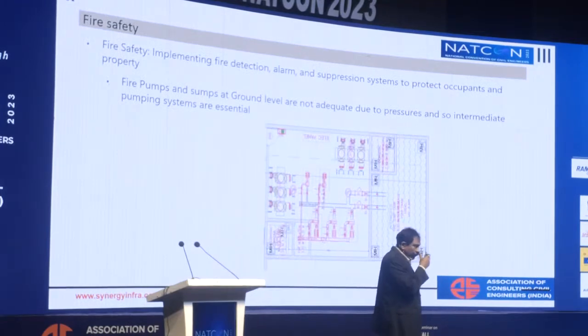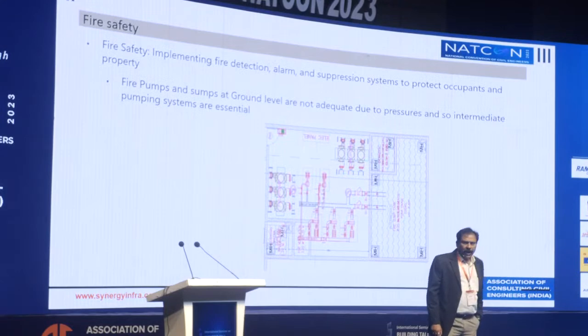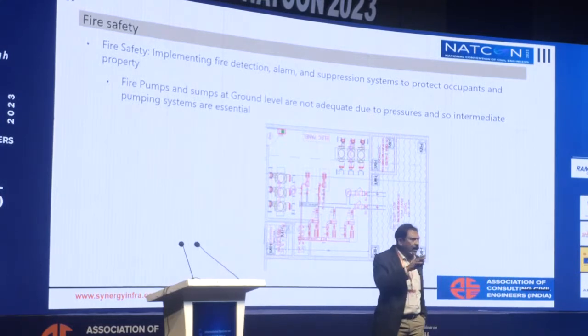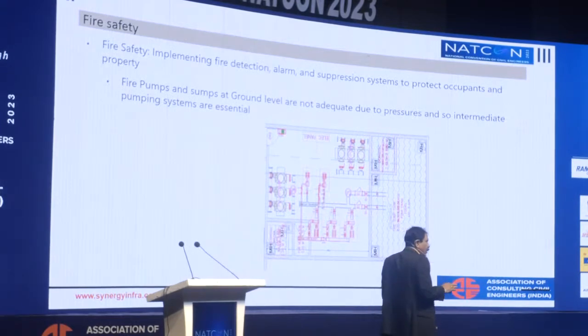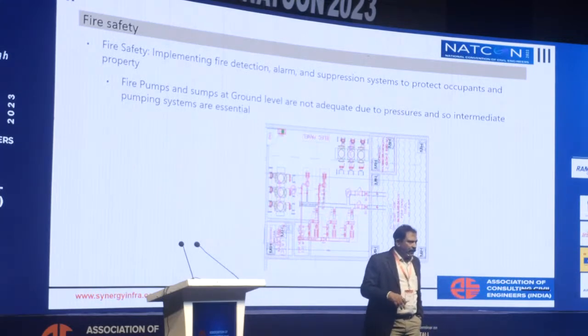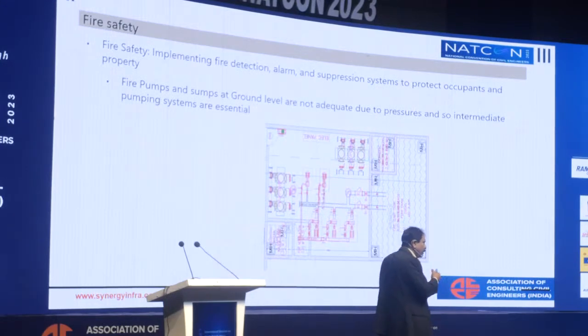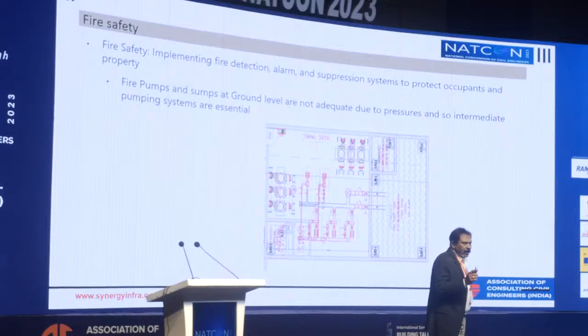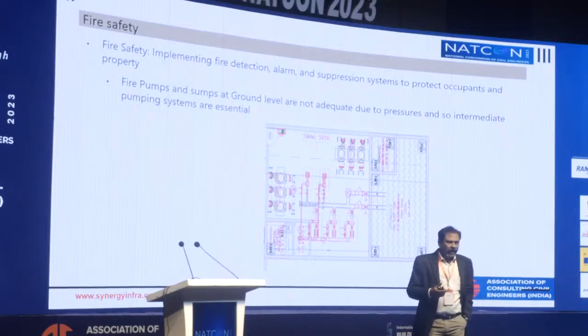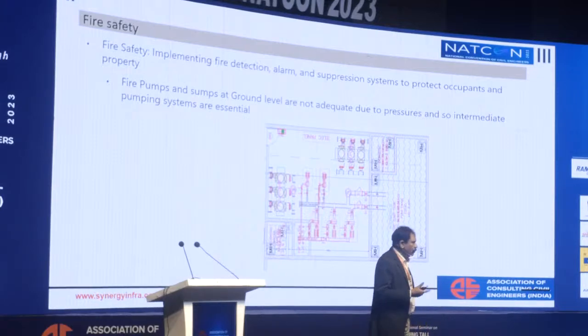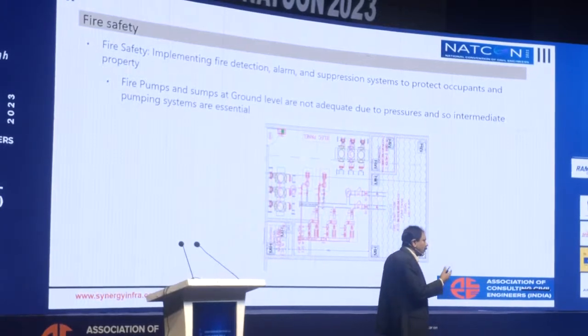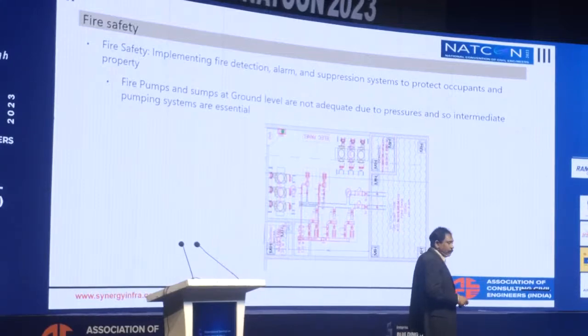One of the important things is when you talk about high-rise or tall buildings, we can't depend on fire pumps located only at ground level. So the NBC code talks about having an intermediate level fire tank, around 100,000 liters, at around 150 to 165 meters, but our fire department is insisting on it for anything above 150 meters, because I am also part of the code committee. The reason it was specified is that the maximum installation control valve for sprinklers generally is rated for 20 bars. So you can go up to 200 meters height. That is the reason 165 meters has been specified as the maximum limit.